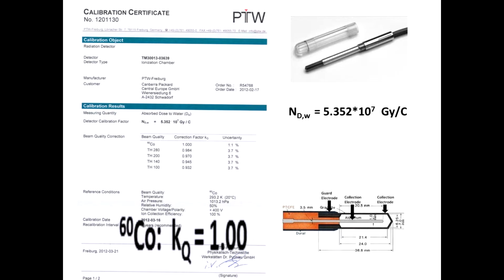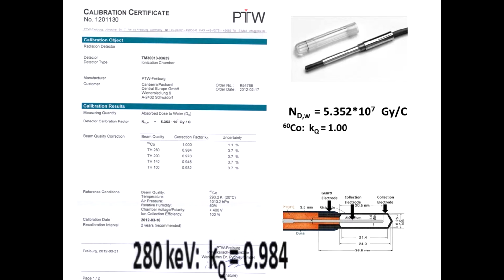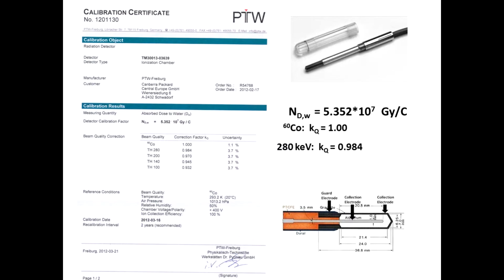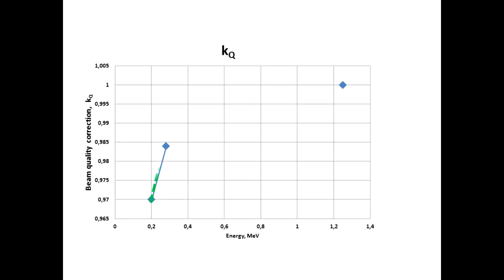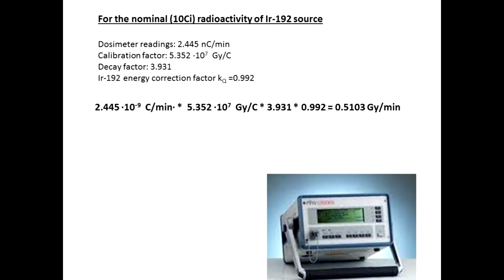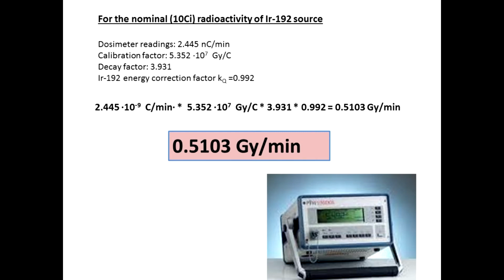The ionization chamber used for absolute measurements should be certified for iridium beam quality. In our case, the farmer chamber was calibrated to cobalt and orthovoltage X-rays, and the energy correction factor for iridium was calculated by interpolating this data. The final result for dose rate at this source to chamber distance for a nominal 10 Curie radioactivity source is 0.51 gray per minute.